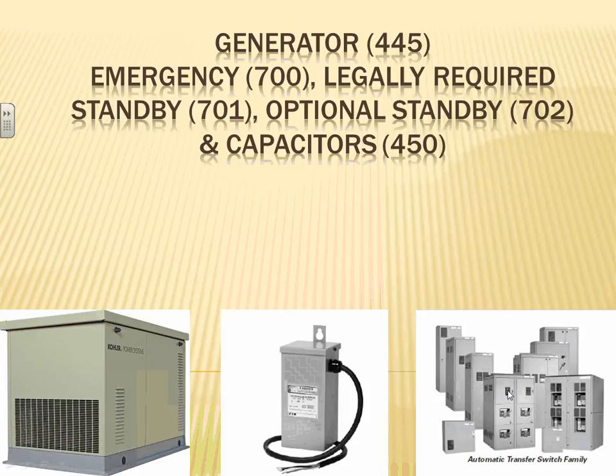And of course, with generators come the automatic transfer switches, because typically that's what we do in smaller projects. So you guys have handouts. In the handouts, I have the PowerPoint presentation that I've done in the past. And like I've done, guys, I always have an SKM coordination. The most important thing about generators is doing coordination with the generator curve, the so-called gen curve. So I have a gen curve for you. I use Cummins software when I size generators, and I'm sure you use something similar. I picked one of the projects that we have done, and I made a copy of it. I'll walk you right through how to size the generator. I'm sure you guys are familiar with it, so please correct me if you see anything different.